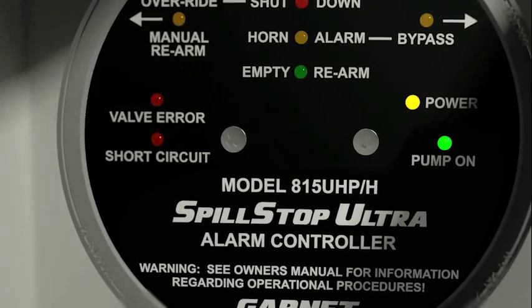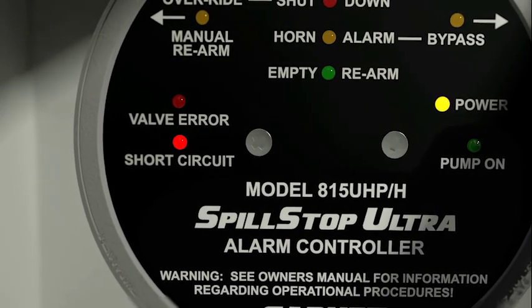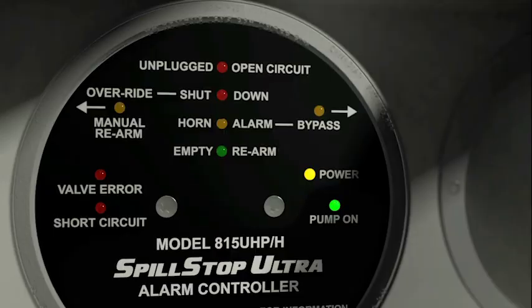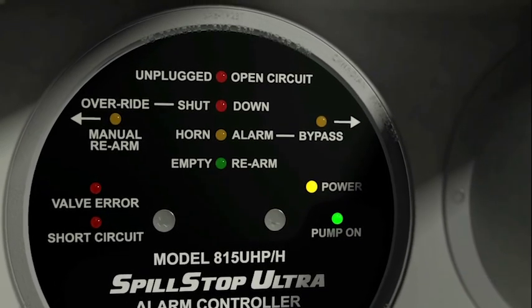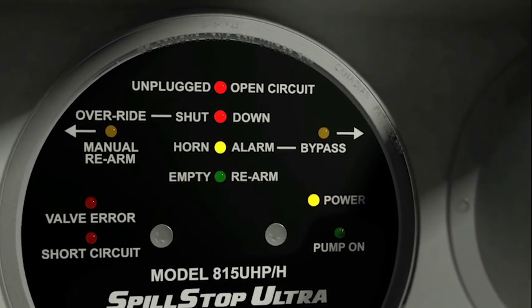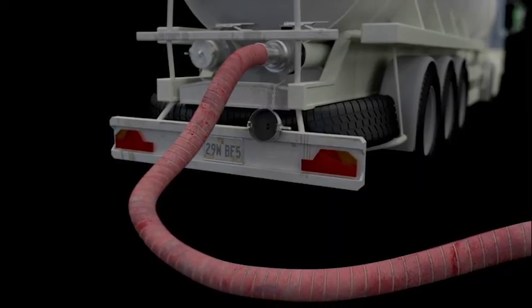A short circuit in the wiring to the gauge lights the red short circuit indicator and shuts down the pump. An open circuit in the wiring to the gauge lights the red unplugged indicator, sounds the horn, and shuts down the pump.